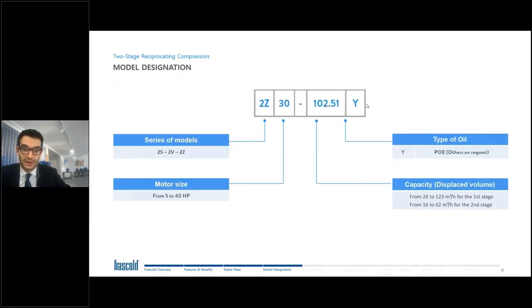We can see here the model designation. The name of the compressor is really simple to understand, because in this case, 2Z30, 30 means the motor size, so the HP at 50 Hz. In this case, it's 30 HP. We have two-stage compressors from 5 to 40 HP. The two numbers divided by a dot give you the capacity of the first and the second stage, in this case 51 and 102. Our biggest is 123. The minimum is 26. Here is the type of oil, in the big majority of cases just POE oil, and others can be available on request.